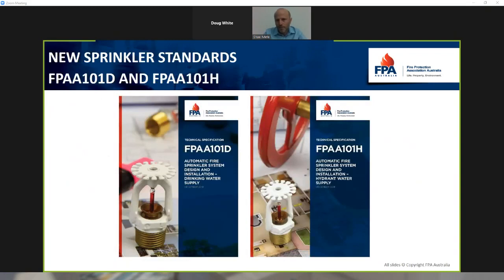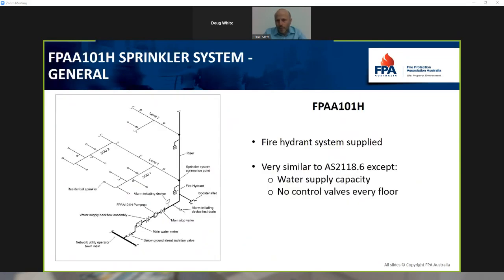So let's have a look at the specifications themselves now. We'll start with the 101H system. H for hydrant. Essentially this is a hydrant supplied sprinkler system, and this one is connected to a water supply, obviously. It's not a dry hydrant system, it's wet. If you're familiar with the 2118 Part 6 systems, you can think of the 101H system very much as equivalent, except for these main 2 factors. There are a few minor ones as well, but these are the main 2.